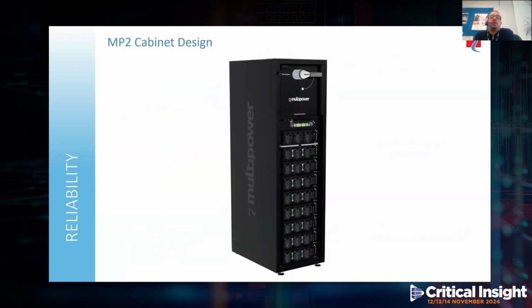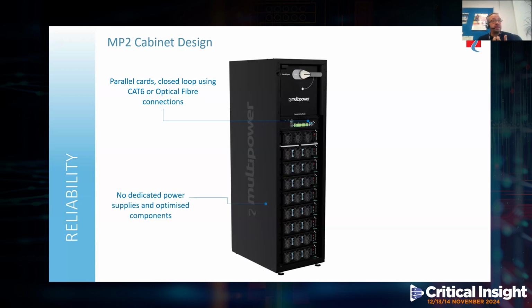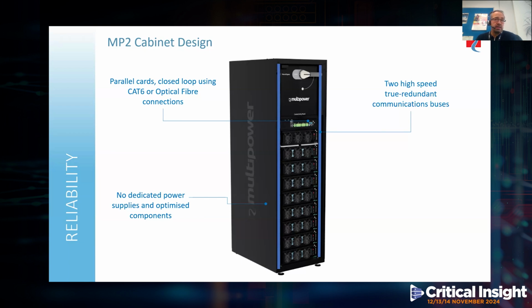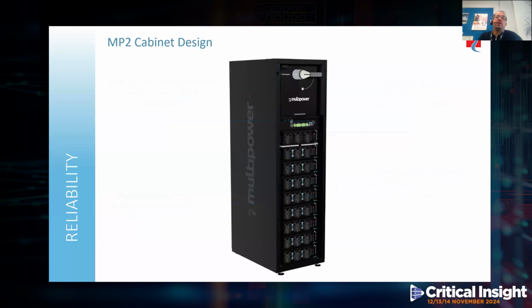Now, of course, no modular system is complete without the cabinet, which contains several key features. There are parallel cards for cabinet paralleling, which is used via a closed-loop communications bus, which can utilize either a Cat6 cable or optical fiber. There are no dedicated power supplies, and so all components have been optimized. The system utilizes a high-speed, true redundant dual communications bus, and all modules are mechanically and electronically interlocked for safety and security. In addition to this, the front doors are all fitted with air filters, which prevents dust and dirt ingress.